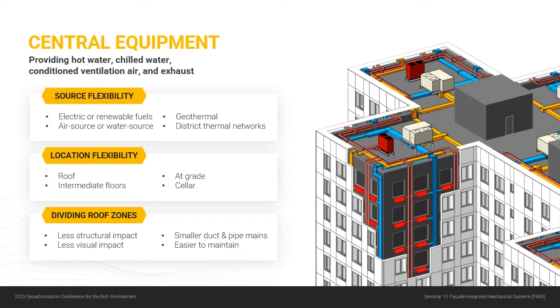An important point to make here is you can see that for a relatively large building like this, we're not putting one giant heat pump, one giant air handling unit on the roof. We're actually dividing it into separate building zones. And there are a few reasons for that. One is it minimizes the structural impact with smaller, lighter, distributed equipment. There's less of a visual impact from the street. You end up with smaller duct and pipe mains, and the equipment is smaller, so it becomes easier in terms of maintenance, because at this point we're talking about really light commercial-grade equipment. We're not talking about large, complex heat pumps and air handling units.